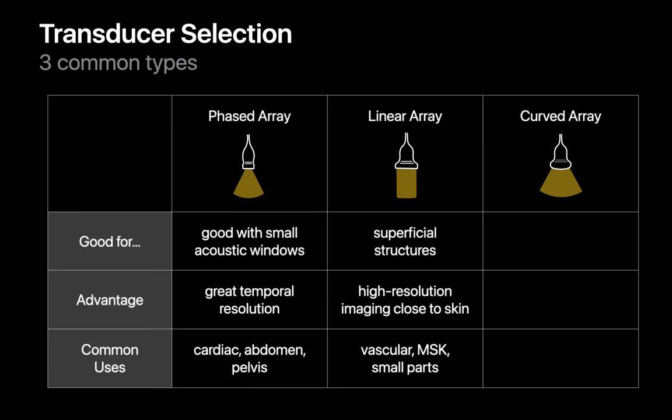Linear array transducers are excellent for superficial structures and can offer high-resolution imaging of tissues close to the skin. They provide a rectangular or parallelogram-shaped image. Although they provide high spatial resolution superficially, their ability to image deeper regions is limited. Linear array transducers are commonly used for vascular imaging, musculoskeletal imaging, and small parts imaging like thyroid, breast, and testicular scans.